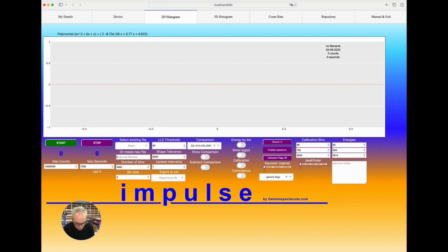So let's do it. Let's create a spectrum called my uranium spectrum. Okay, and we arbitrarily give that 4092 channels. Any arbitrary number will work. And the pitch per channel is 2, and we'll later on see that this is about the right pitch to see the whole spectrum within the screen. And we call it the bin size, but it's essentially the pitch of the channel.